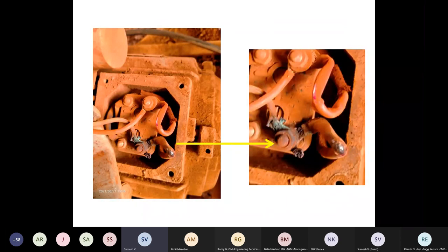When we open the terminal cover of the motor, we could see that the insulation of the wire was damaged due to rubbing with the terminal cover. It happened because the motor was not rigidly fixed. Due to the continuous vibration, the insulation of the wire was damaged, and the supply came to the body of the motor, and the person who accidentally touched the motor body got electrocuted.